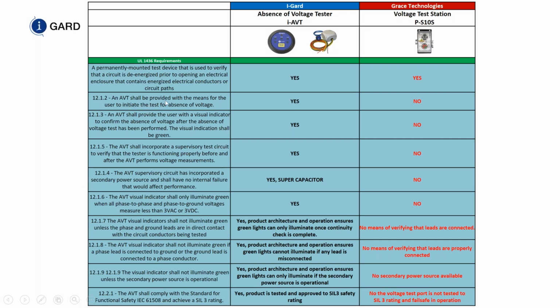An AVT shall provide the means for a user to initiate the test in the absence of voltage. Yes. No, there's no test functionality here. This is a manual process; this is an automatic process. An AVT shall provide the user with the visual indication to confirm the absence of voltage.